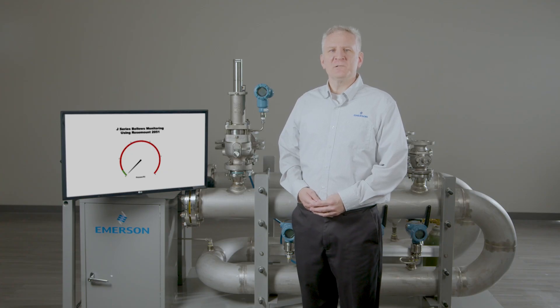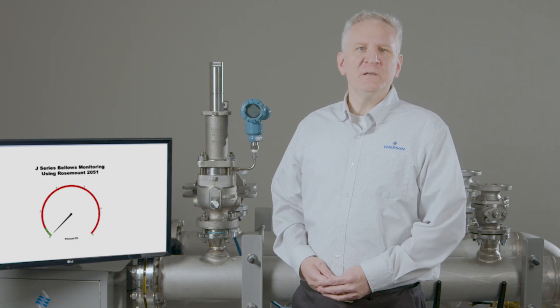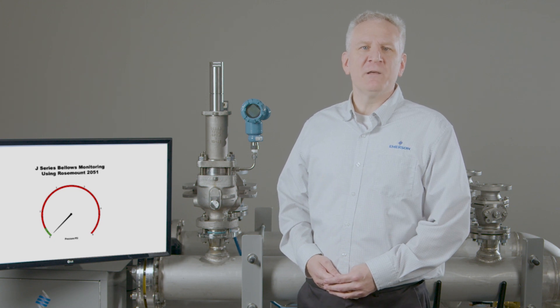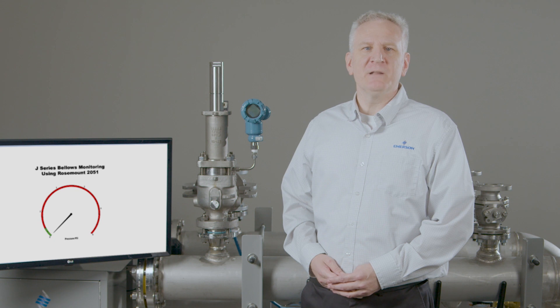In addition, the bellows serves as a barrier to isolate critical valve components inside the bonnet chamber from exposure to corrosive media. Furthermore, in the event of a bellows failure, the bonnet vent must remain open to atmosphere to ensure pressure is not accumulated in the bonnet, which could alter the valve's set pressure.